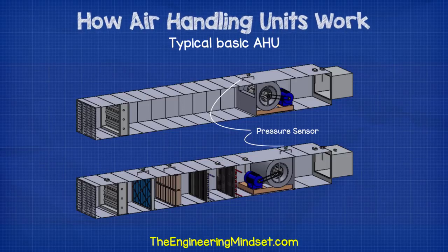Across the fan, we'll also have a pressure sensor. This will sense if the fan is running. If it is running, then it will create a pressure difference. And we can use this to detect a failure in the equipment and warn the engineers of a problem.